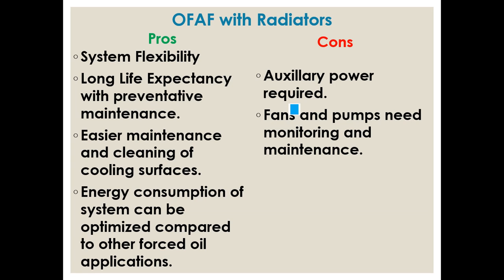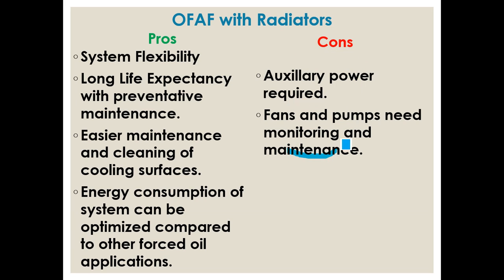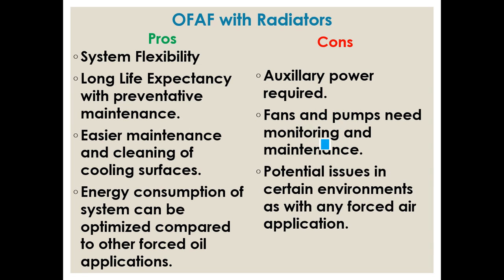The disadvantage is auxiliary power - you will require additional power to run the fan motor and the pump motor. So to run the fan and the pump, auxiliary power is required. We will be requiring some 250 volt or 415 volt supply for that, so auxiliary transformers will be required. These systems also require continuous monitoring and maintenance.